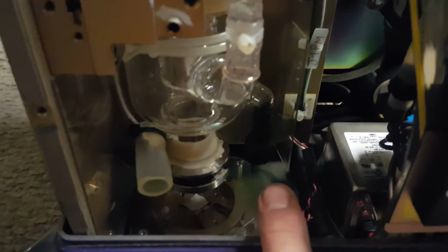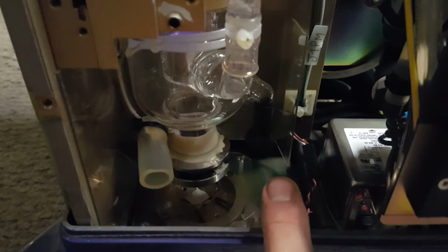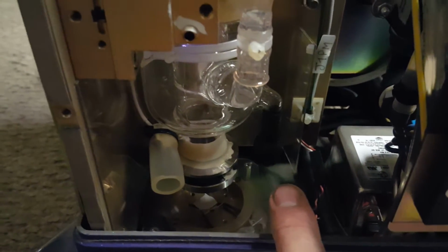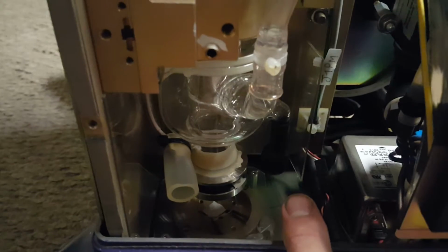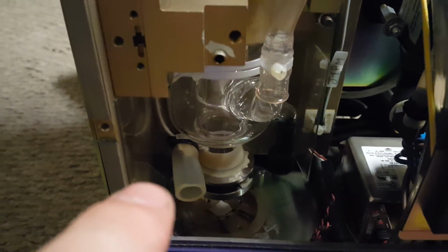Now, down here there is a port right here. I'm not going to reach in very far, there's 20,000 volts there, but that, I believe, is the gas port, so this laser tube can be serviced. That right there is an electrode. That right there is the liquid cooling. And up here you can see we have the liquid cooling port, the electrodes, and the outputs.